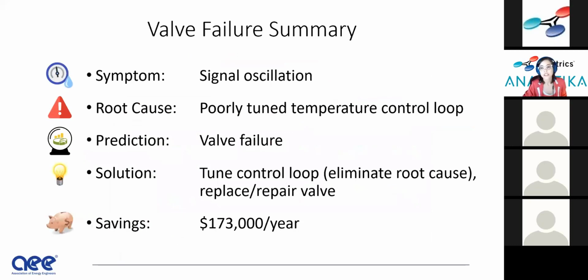So here the symptom was signal oscillation. Sometimes we can actually see, like I mentioned before, a set point disagreement. A preheat set point and a final discharge air temperature set point might be so close together without any deadband that you're constantly oscillating the valves to try to meet those two set points together. So we can sometimes predict oscillation before it even occurs by looking at set points and saying, in wintertime, you're going to have a problem. But usually we look at oscillation.